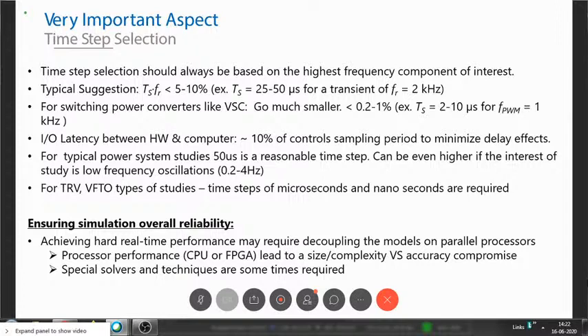If you don't have any switching converters and you are looking at a simple 50 hertz system without much dynamics, you would know that unless you have specific nonlinear loads, you would probably be looking at the 50 hertz signal only. But if you have a nonlinear load like a diode based rectifier and so on, you can assume you can have 5, 7, 11 kind of harmonics. So what is the harmonic to which I need to filter my system is an engineering judgment. It's an engineering design question.